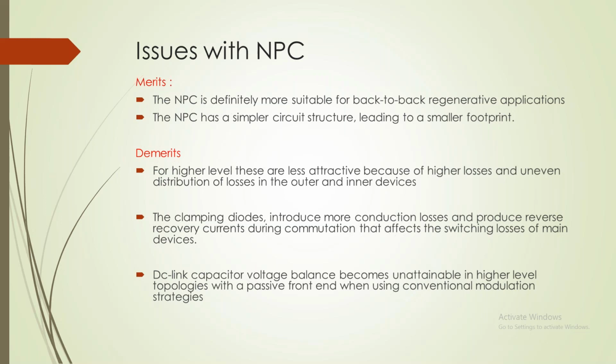for NPC because there are freewheeling diodes. So there are feedback diodes. They will ensure that the reversal of power flow is possible. The bidirectional power flow is possible. Of course, it may be possible in others also, but it's not as good as in NPC. So NPC converters are preferred in back-to-back regenerative applications, right?